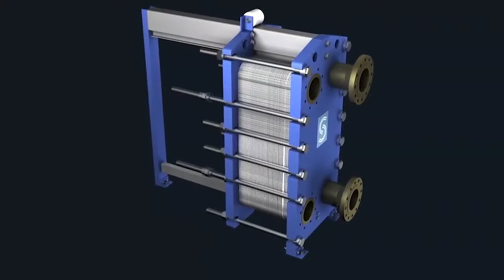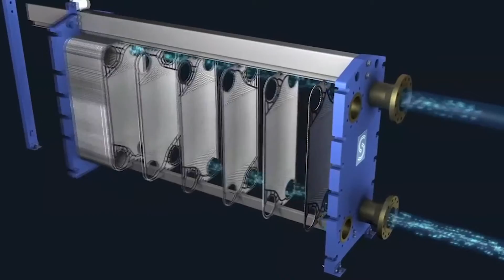While we are talking about heat, it's important to mention heat recovery. Plate heat exchangers were recommended for installation into the AHUs. These consist of simple air-to-air heat exchangers that operate on the basis of hot extract air warming a metal plate, which in turn warms the incoming air supply. The potential thermal load saved is approximately 42,000 euro with an approximate payback of less than 1 year.